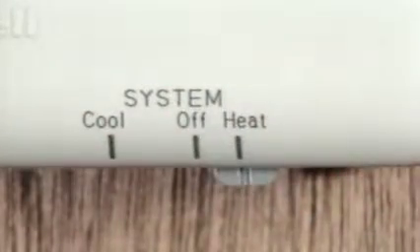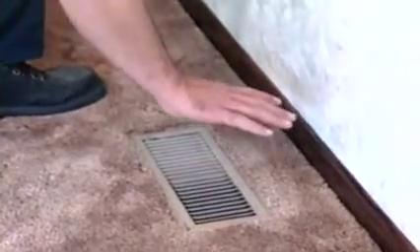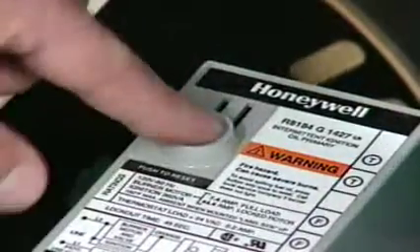Customer says: This morning it was really cold here, so I turned up the thermostat but nothing happened. As the customer said, the thermostat is set and calling for heat, but the furnace is not operating. When the fan switch is moved to the on position, no airflow can be felt at a supply register. A quick visual inspection at the furnace reveals that the disconnect is on, the fuse is good, and the safety switch on the primary control is not tripped.